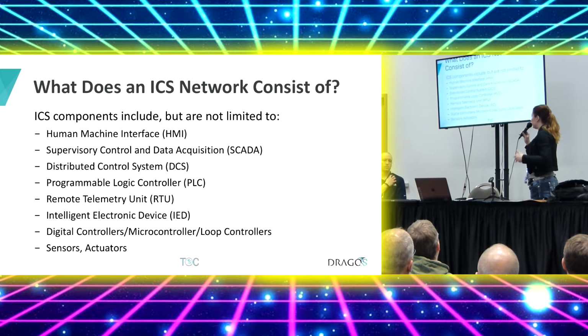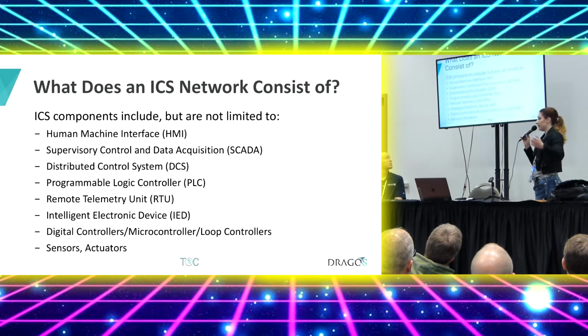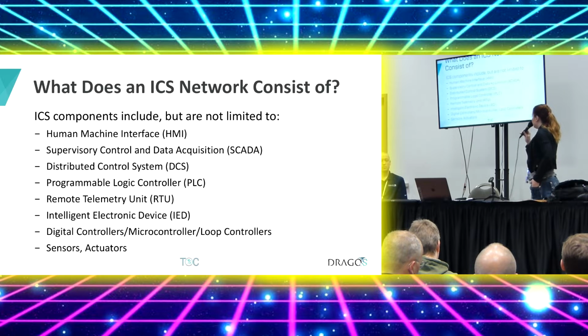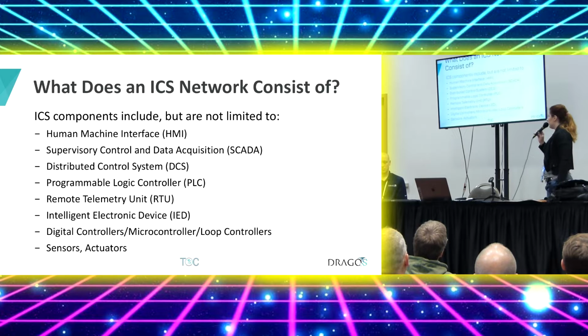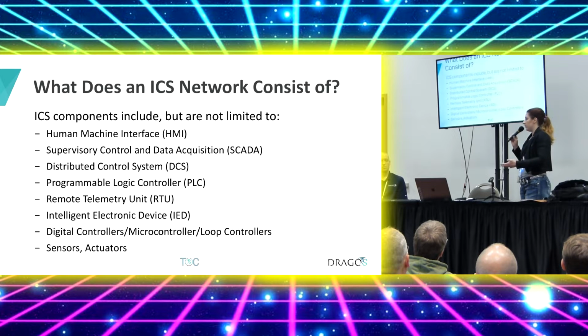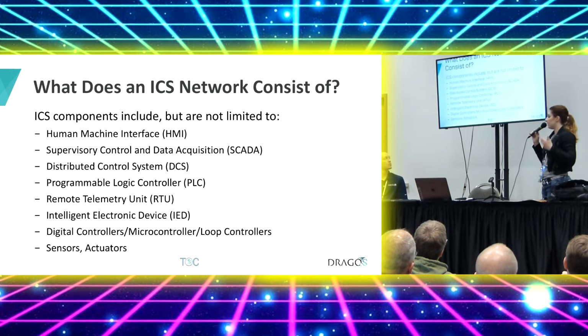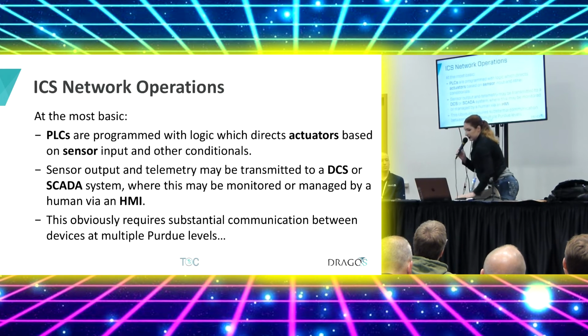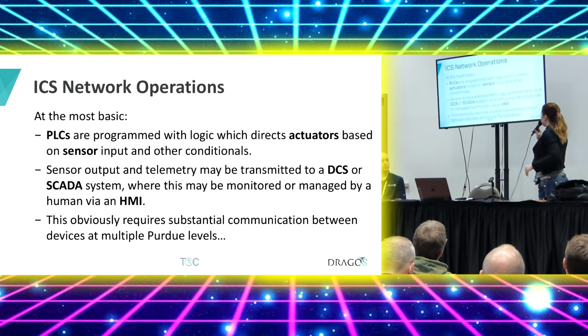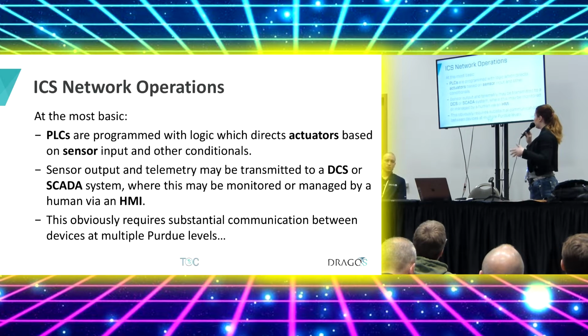We have RTUs, which essentially perform the same function, acting almost like a terminal server - they pipe data back to a central controller, which issues commands back. Then we have various types of physical controllers with limited digital function: microcontrollers, loop controllers that make sensors and actuators do things. So we've gone down the list from very technical human-controlled systems collecting digital data, all the way down to switches. The important thing to note is that PLCs are programmed by simple logic based on very simple inputs, usually Boolean yes or no, or sensor data, looking at levels and various conditionals in logic.